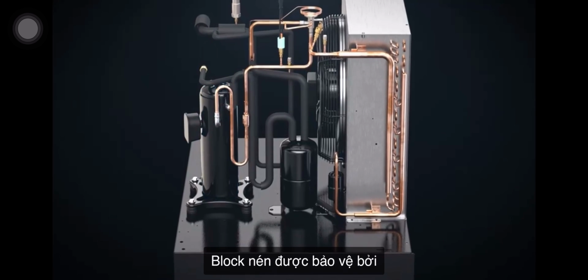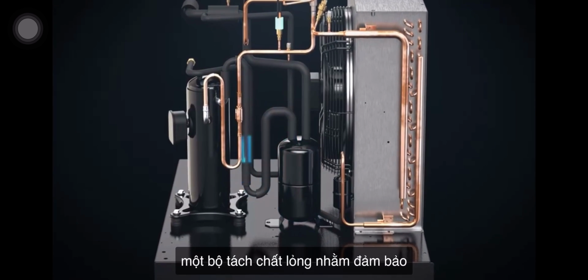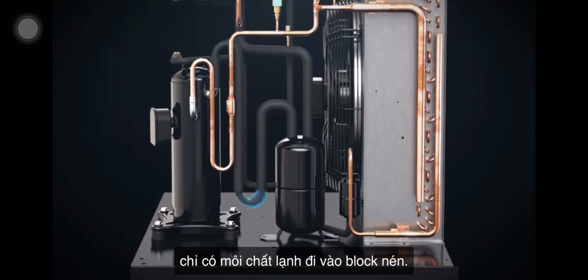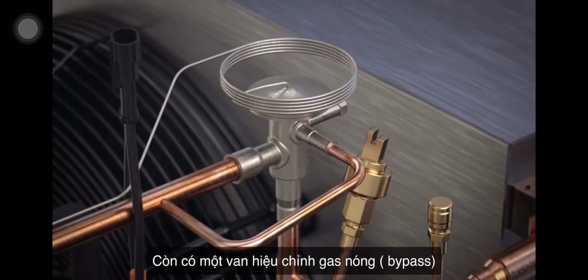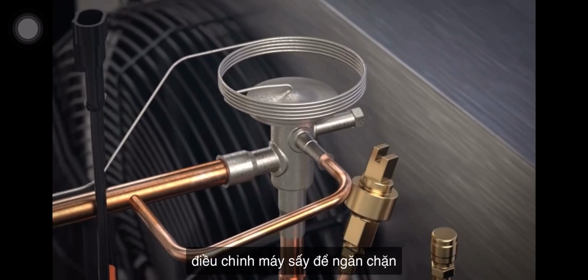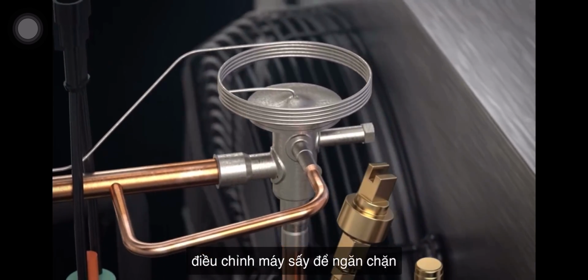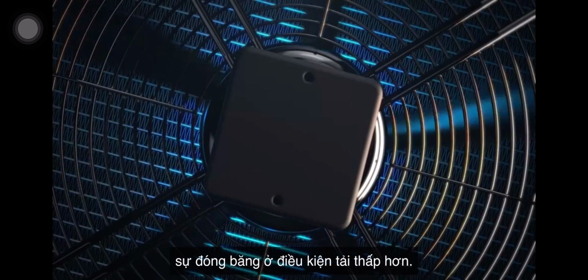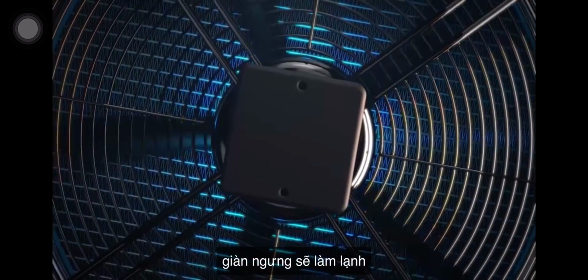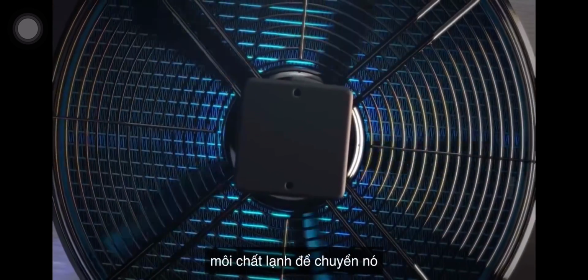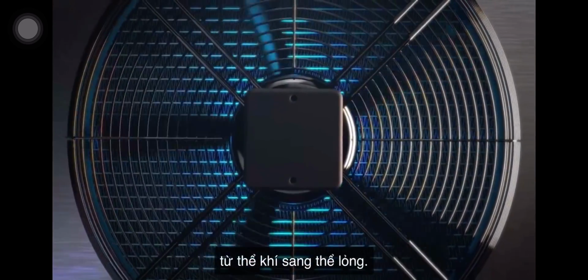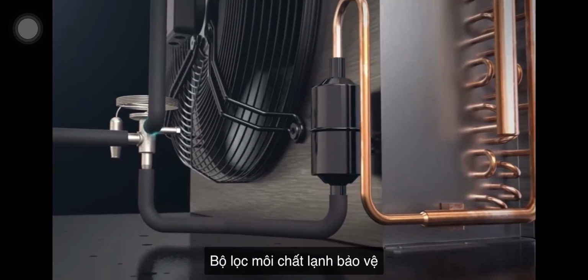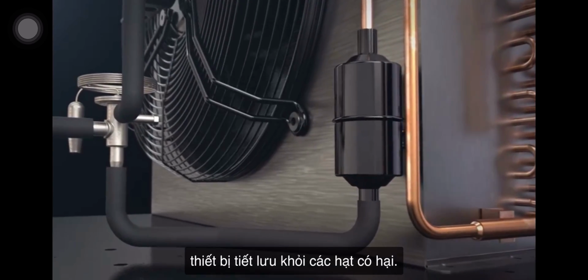The compressor is protected by a liquid separator that ensures only refrigerant gas enters the compressor. There's also a hot gas bypass valve, which regulates the dryer to prevent freezing at lower load conditions. After compression, the refrigerant condenser cools the refrigerant so that it changes from a gas to a liquid. A refrigerant filter protects the expansion device from harmful particles.